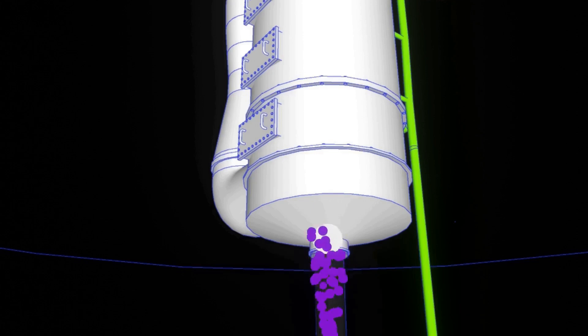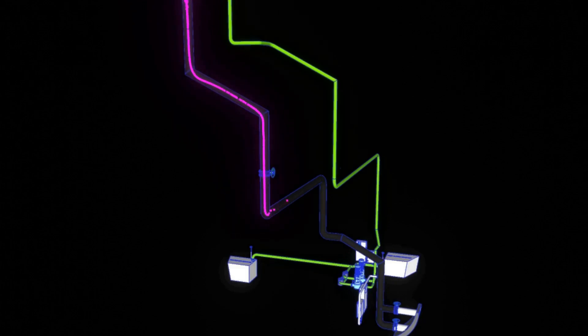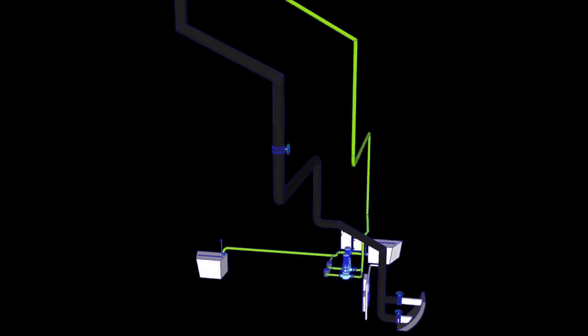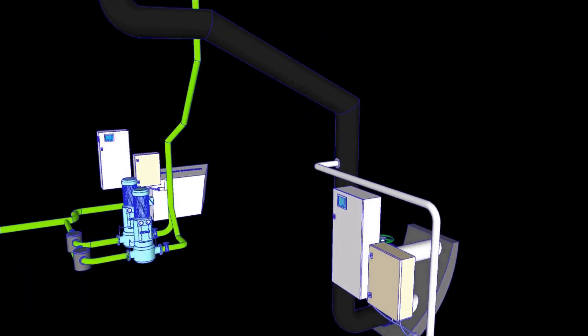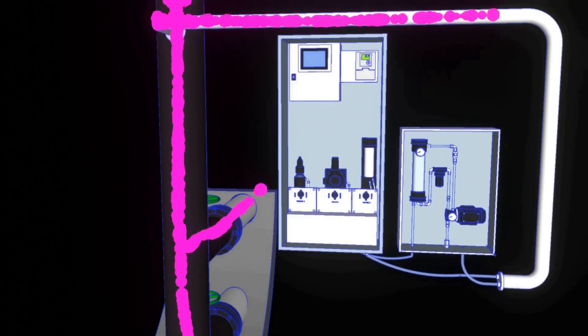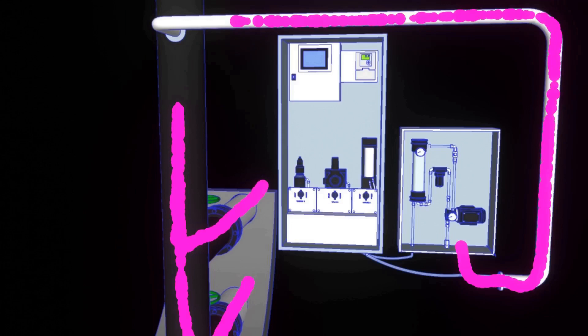All wash water from the main chamber and venturi is being drained from the bottom part of the scrubber. The drain line is made up of glass reinforced epoxy which is highly resistant to corrosion. Before the wash water goes overboard, it is then again measured for the values of pH, PAH, and turbidity.